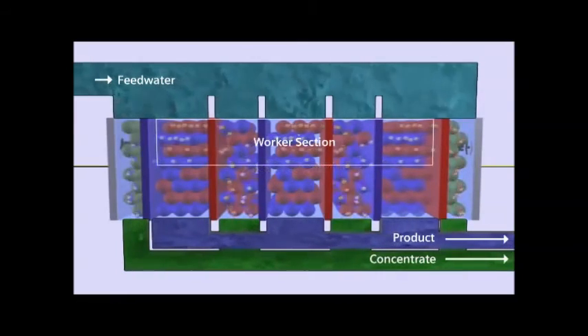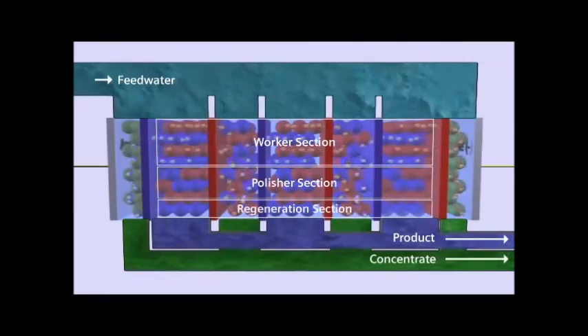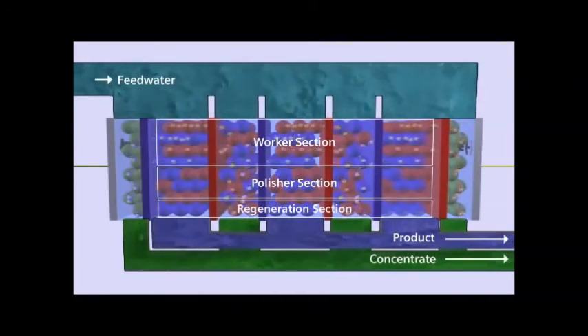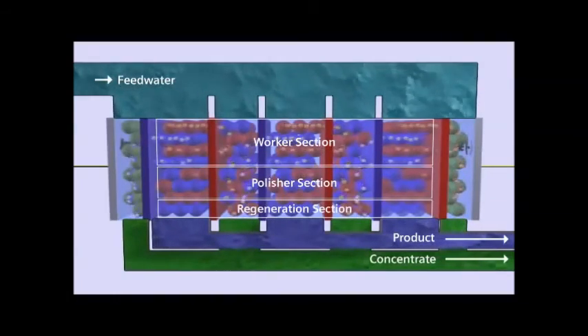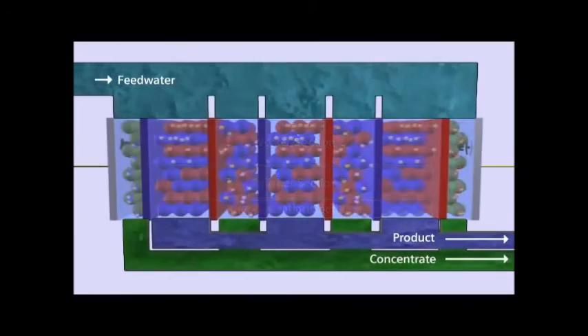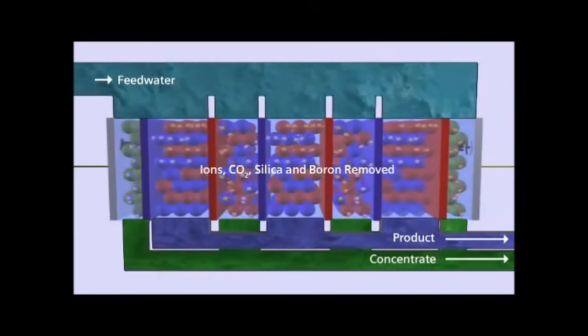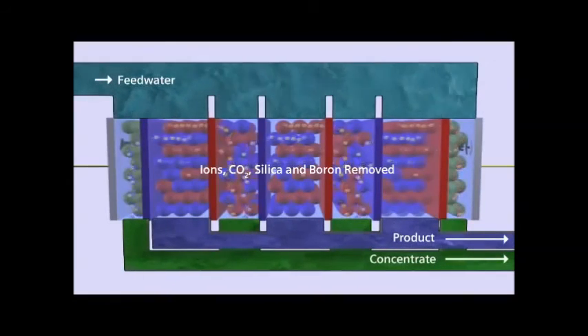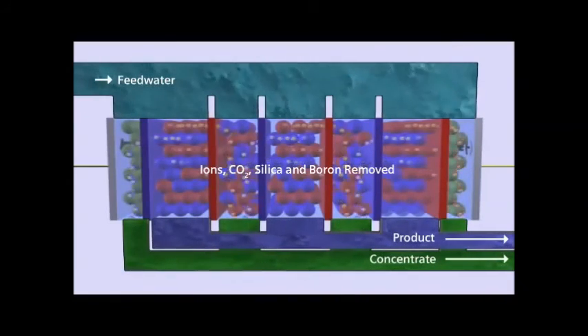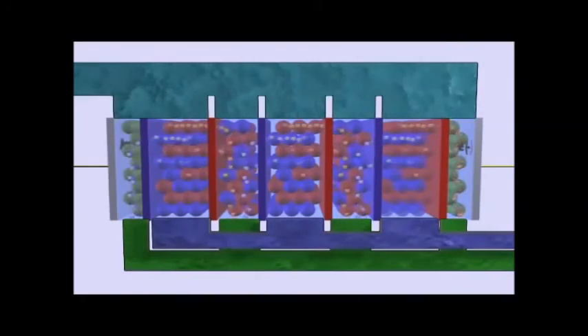You essentially have a worker and polisher combined into one unit which constantly regenerates. IonPure CEDI systems are more effective than other electrodeionization systems when it comes to removing dissolved materials such as salts, acids and bases, as well as weakly ionized materials such as dissolved organics, silica, boron and carbon dioxide. This continuous regeneration process also eliminates pH shock and greatly extends the life of the resins.